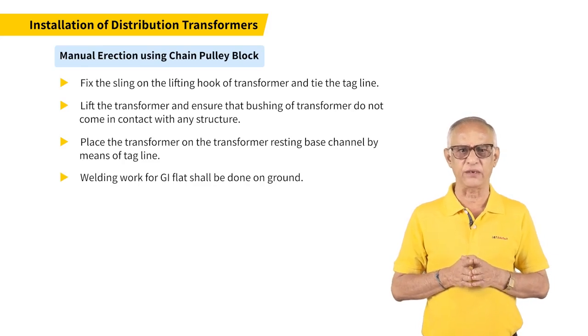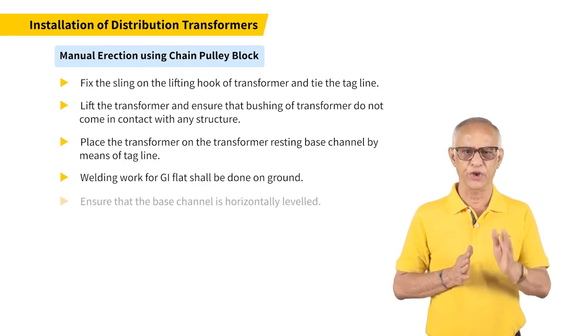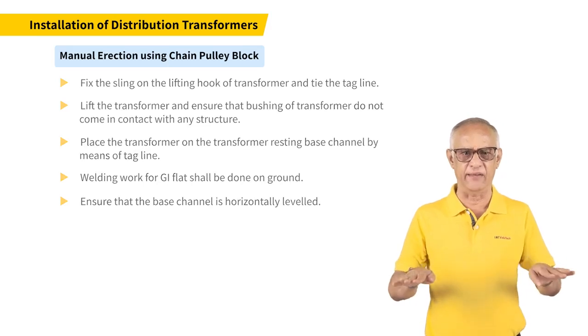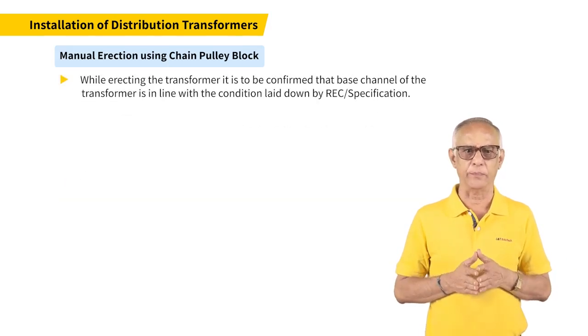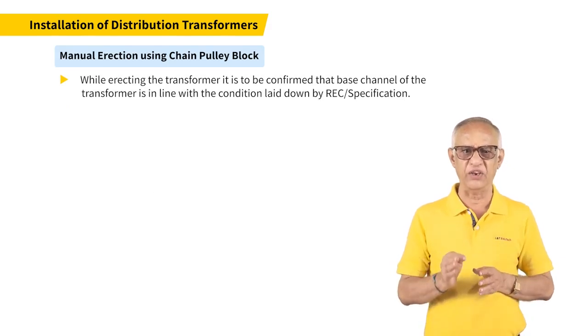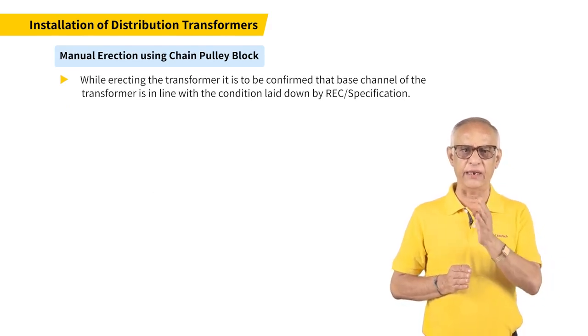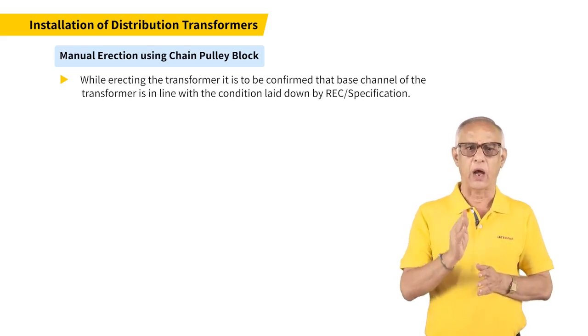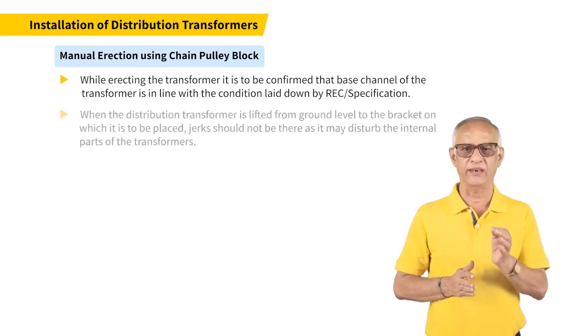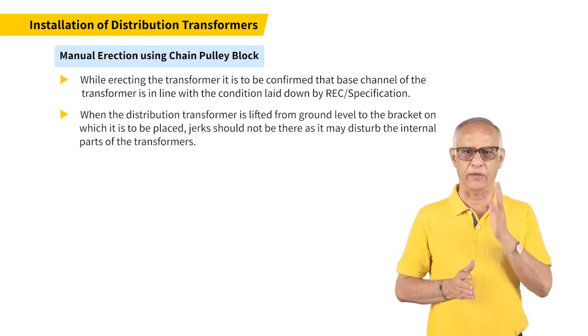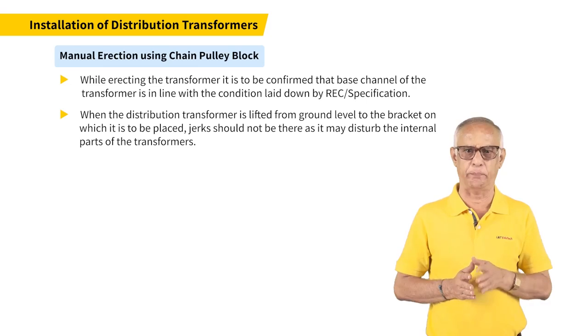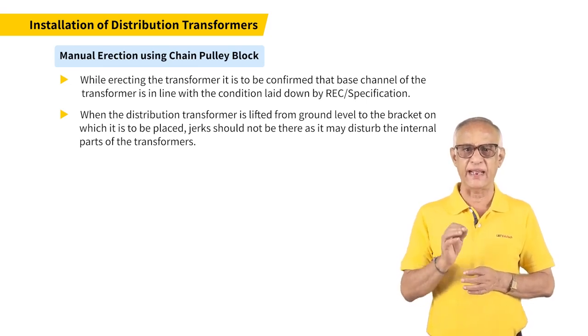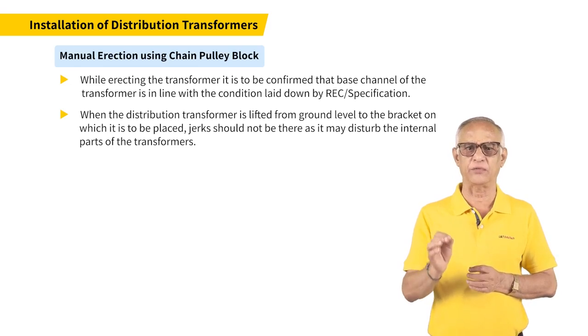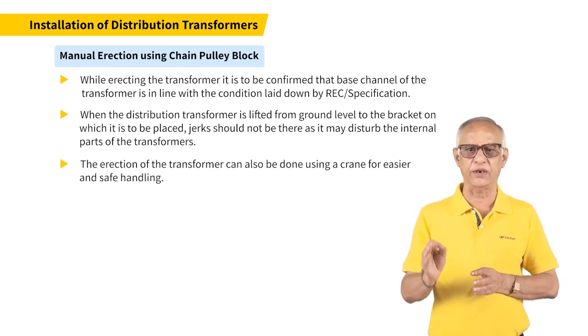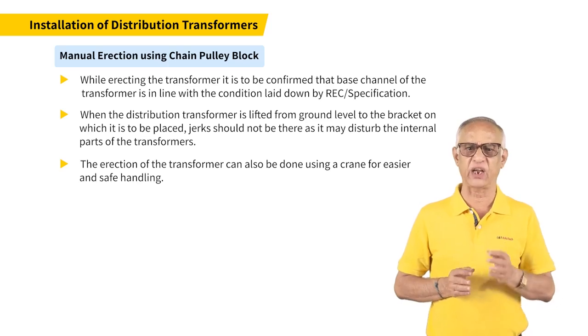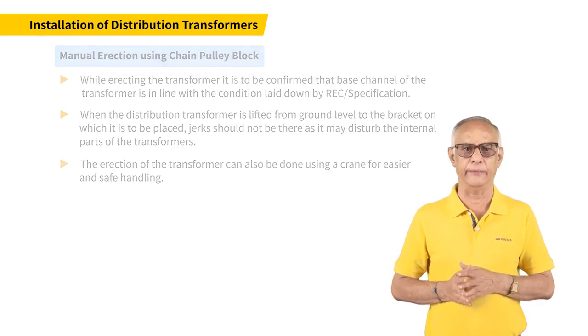Welding work for GI flat shall be done on the ground. Ensure that the base channel is horizontally leveled. While erecting the transformer, it is to be confirmed that the base channel of the transformer is in line with the conditions laid down by REC specification. When the distribution transformer is lifted from the ground level to the bracket on which it is to be placed, jerk should not be there as it may disturb the internal parts of the transformer. The erection of the transformer can also be done using a crane for easier and safe handling.